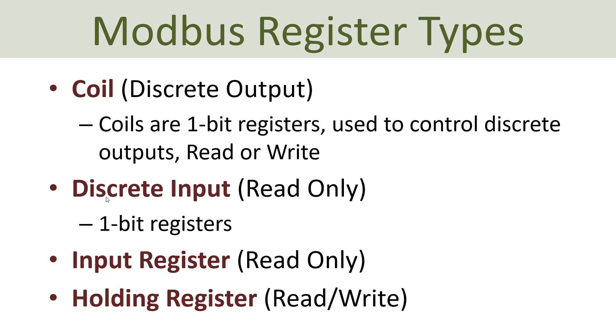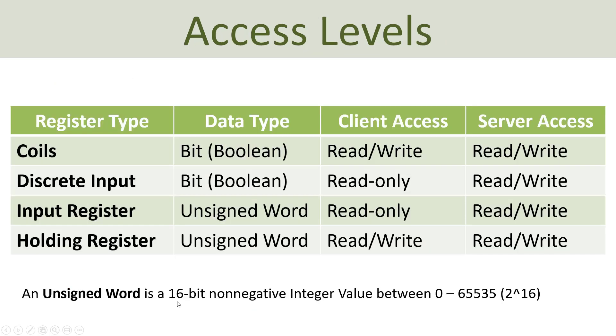In Modbus, we have four different types of registers: coils, discrete input, input registers, and holding registers. Coils and discrete inputs are the data type boolean or bit, so these are true or false values, or zero or one.